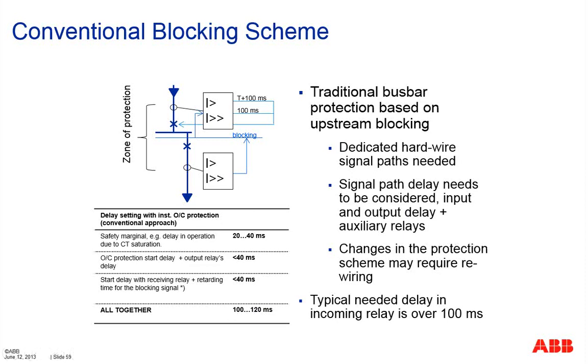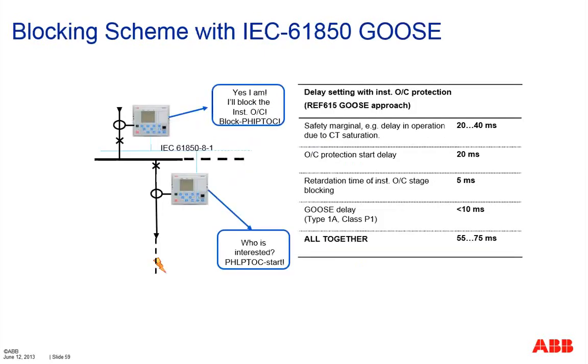However, in the modern communication scheme, modern relays also support the substation communication protocol IEC 61850, and in particular GOOSE, Generic Object Oriented Substation Event, which is relay-to-relay communication through the substation automation Ethernet network. With that, you can reduce the amount of time.